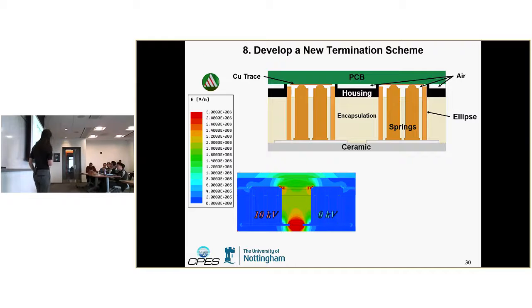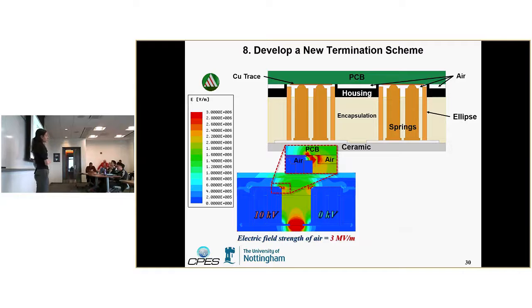So we looked at electric field simulations. If you have 10 kV between here and here, you can see internally, because of those springs, there's not a lot of significant electric field. But still in these air gaps you have high electric field that exceeds the breakdown strength of air. So we looked at some field grading methods.